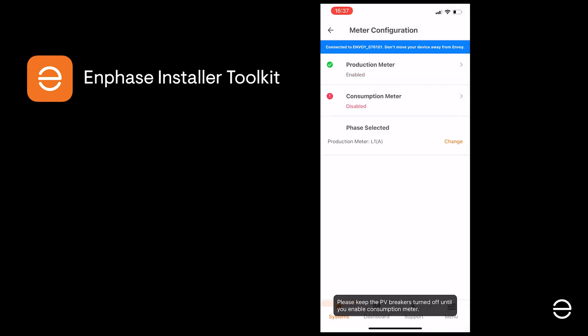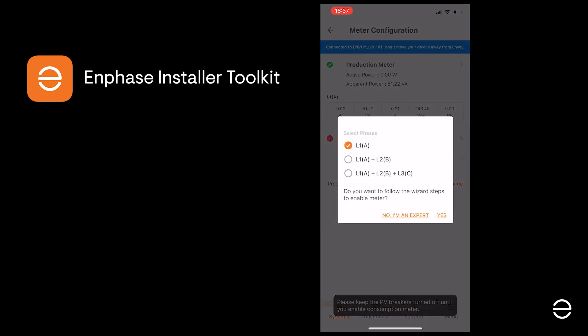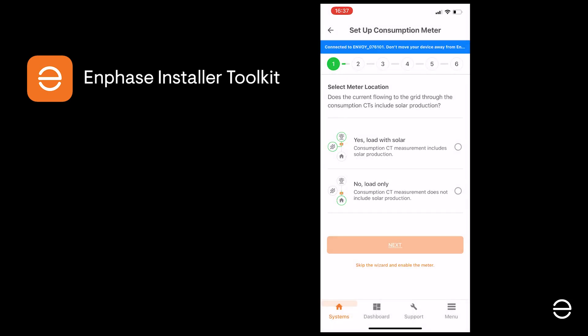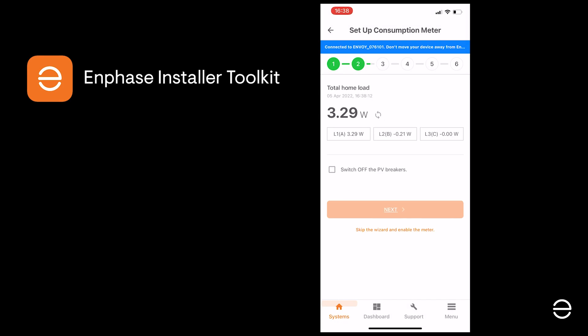Make sure you leave the PV breakers off for now. You can now configure the consumption meter and as before specify the phase type. You then need to select whether you want to measure consumption with or without solar, depending on where you have placed the CTs. In the vast majority of cases this will be between the PV system and the breaker box, as in the current example, so we're going to select Load with Solar. Click Next and you should see the consumption load appear. You need to switch the PV breakers off and check that the load indicated is close to the actual consumption in the home at that moment, and that indicated on the home meter.